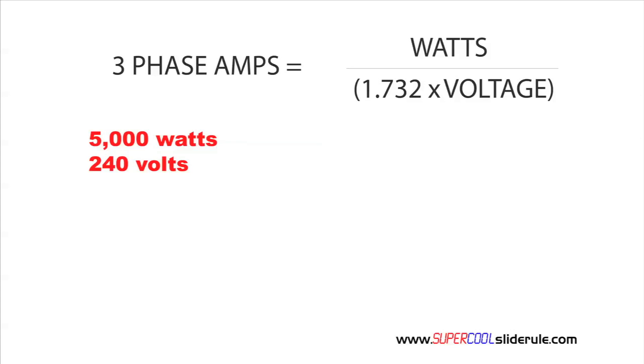Our unknown are amps. So, amps are going to be equal to 5,000. Now, never forget when you have something in parentheses, you must do everything in parentheses first. So, it is going to be 5,000 divided by 1.732 times our voltage was 240. So, we end up with amps are equal to 5,000 divided by 415.68.